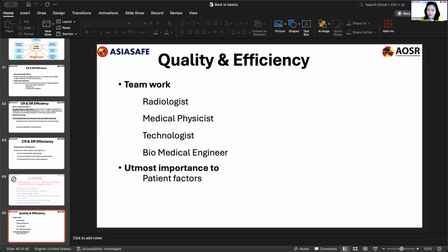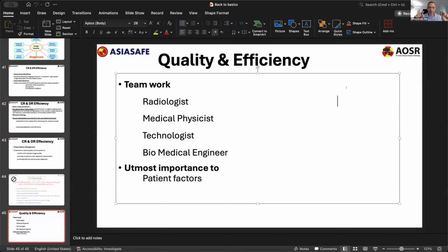How can I know that this is good enough or not? That's a great question. So DI values, ideally you'll choose DI over EI, and you need to work with your PACS team. Oftentimes with your hanging protocol, you can have it so that the DI will appear in one of the corners. So you might see kV, mA, and then the DI value would be listed, in which case, as long as you understand that that value is DI and it says 0 or +5, you would then be able to make that assessment.